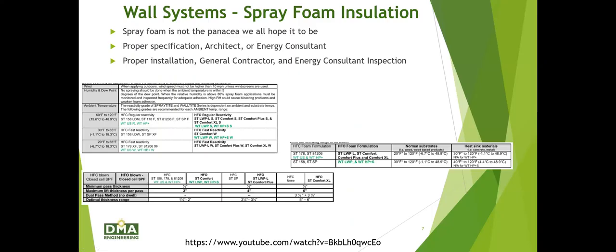How many times do we see a specification that says spray foam insulation to an R70 wall? So it's 6 inches at 6.5 inch foam. That's an R39. So how are we getting an R70? That's got to be 12 inches of spray foam insulation.